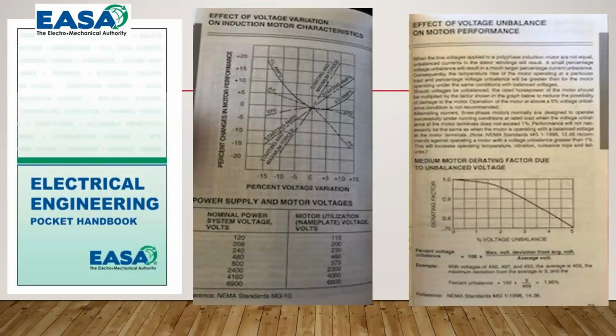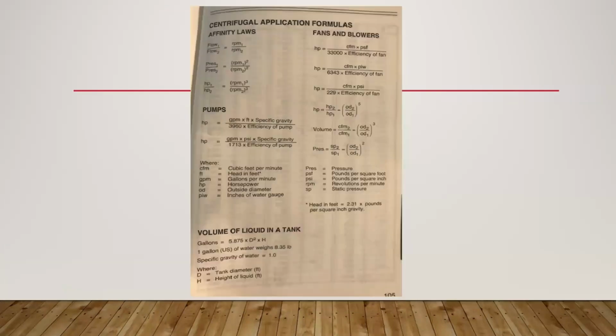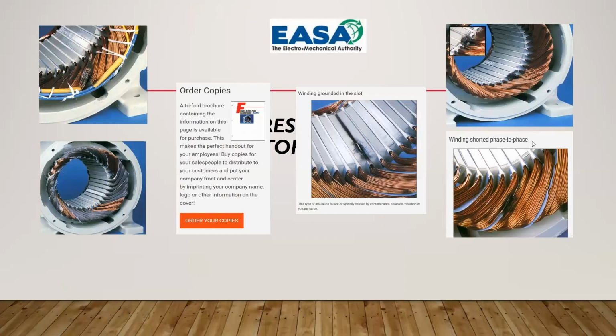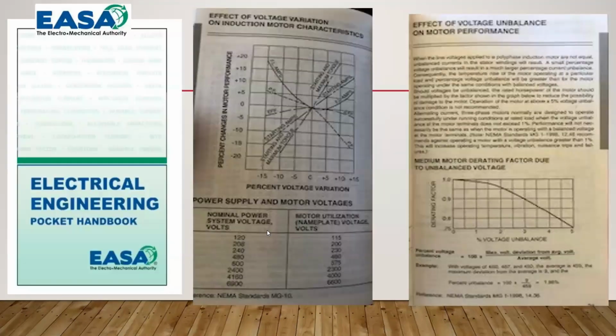And they've got a lot of really good information to help you, even on centrifugal pump applications, volumes, flows, to get back to those efficiency points. They have a lot of data so you can find out what truly caused motor failure. So this happened to be, you can see the imbalance in phase power on those three phases. This is going to be a 4-pole winding. You've got one set of windings here that weren't very well used. That means this motor was being loaded on these phases heavier than on the other, and over a period of time, an imbalance just smoked the winding. There are spiking issues, when the voltage transients between phase to phase, and this is a very handy tool. You can get a copy of this, if you want, also.